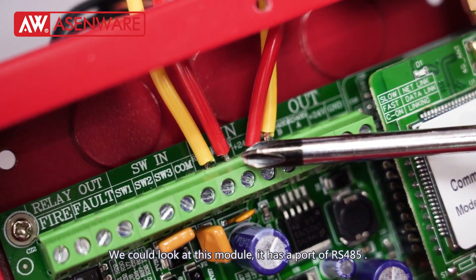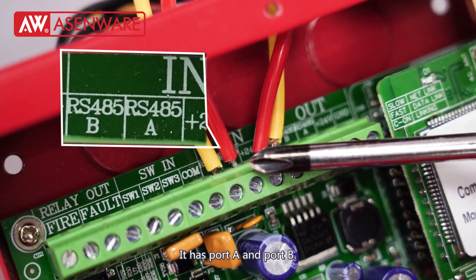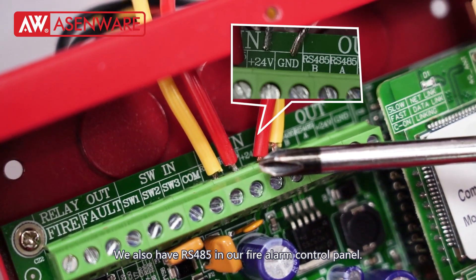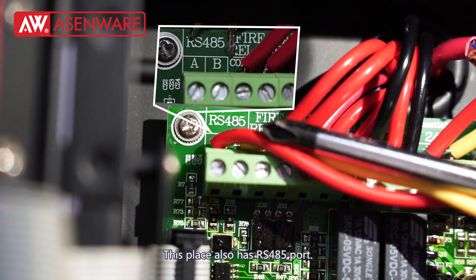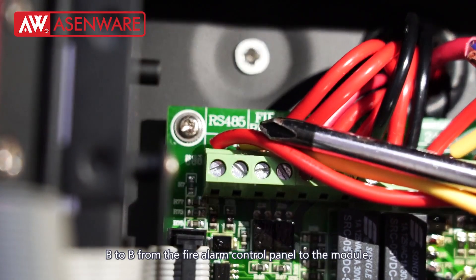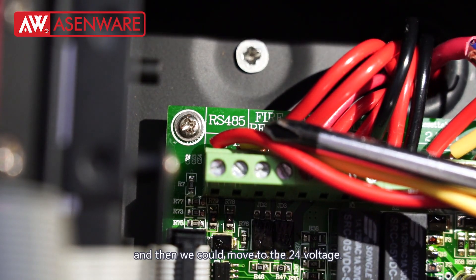We can look at this module. It has a port of RS-485 — port A and port B. We also have RS-485 in our fire alarm control panel. This place also has an RS-485 port. So we can connect A to A and B to B from the fire alarm control panel to the module.